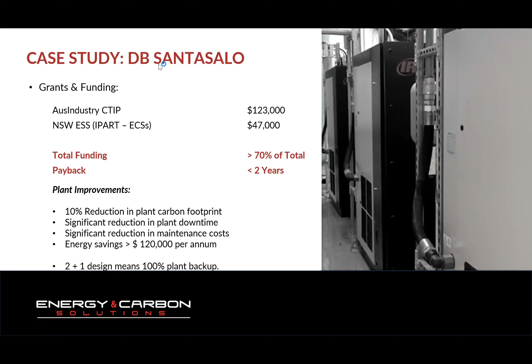The plant improvements, well, we had 10% reduction in plant carbon footprint, significant reduction in plant downtime because we had duty standby on site, significant reductions in maintenance costs because the 160 kilowatt VSD didn't need new motor, didn't need new VSD, and didn't need new air end, and the savings were greater than $120,000 a year per annum. And with the 2+1 design that we've got here, the 3 Ingersoll Rands, we could run the plant on 2 out of any of the 3 machines. And they all had heat recovery, so that didn't affect that process. Next slide, please.